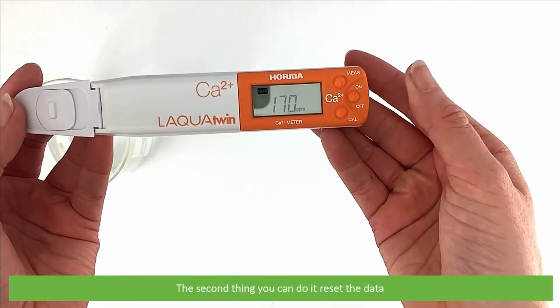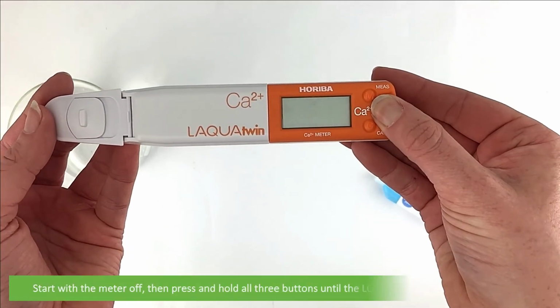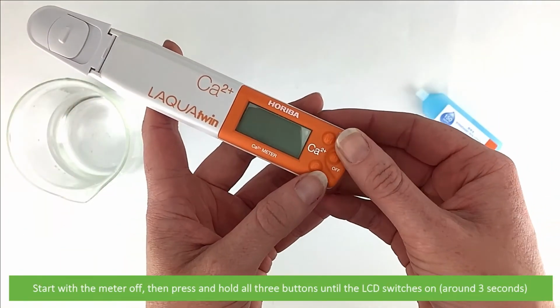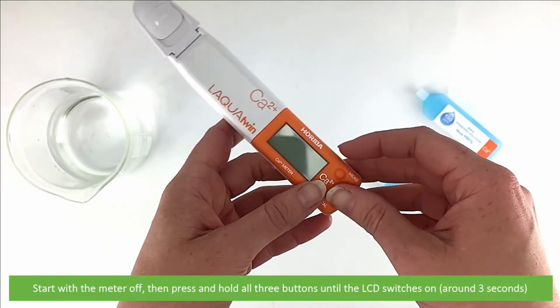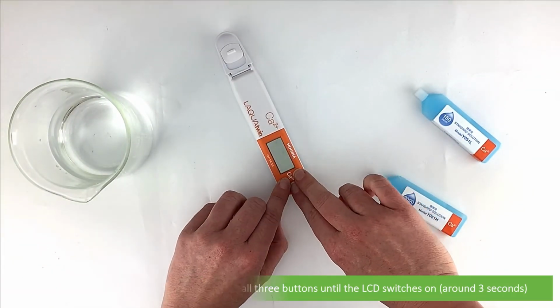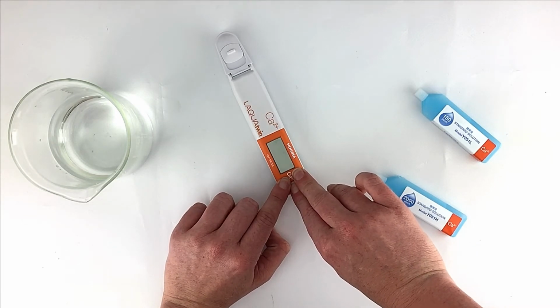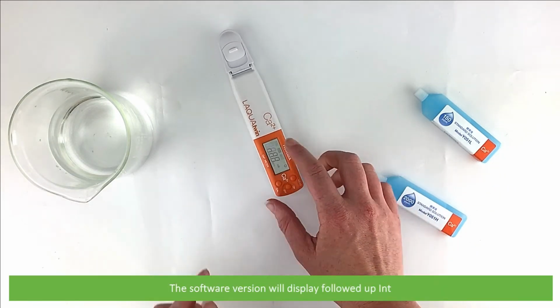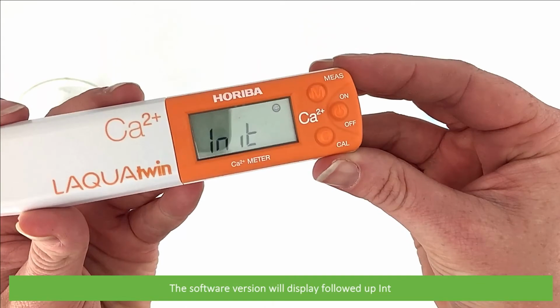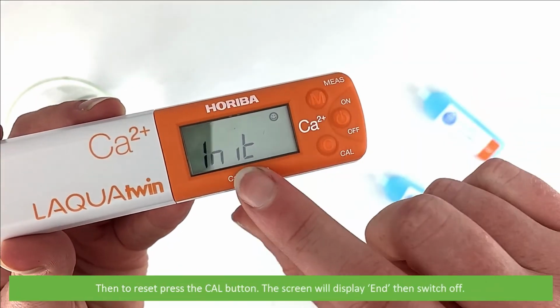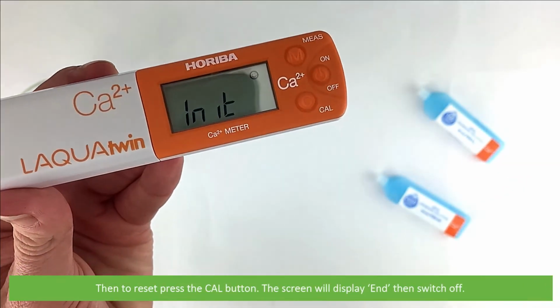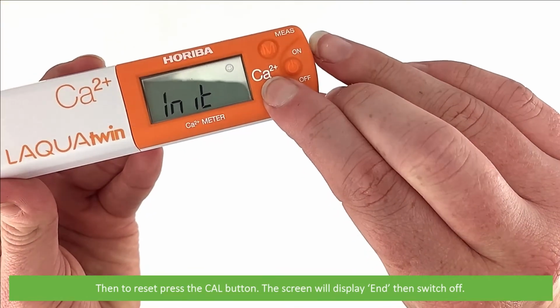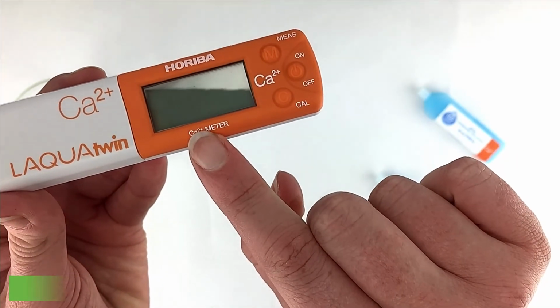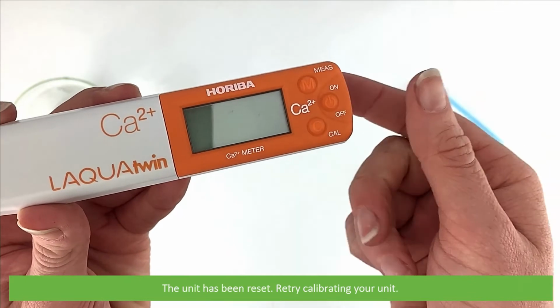The second thing you can do is reset the data. To do this, start with the meter off, then press and hold all 3 buttons until the LCD switches on. The software version will display, followed by INT. Then, to reset, simply press the Cal button. The screen will display end, then switch off. The unit has been reset. Retry calibrating your unit from here.